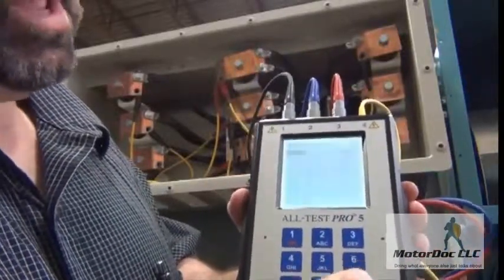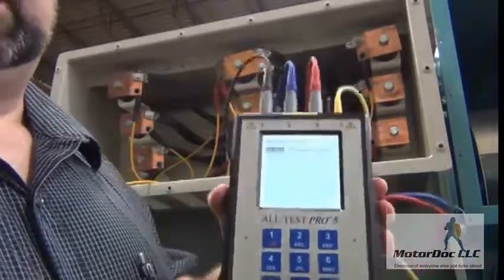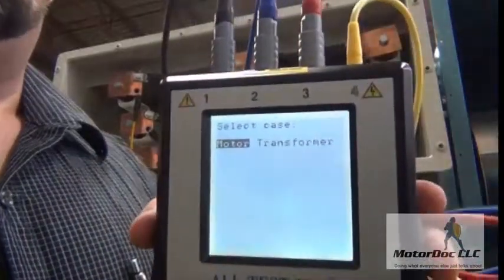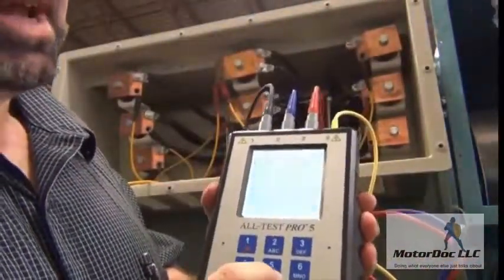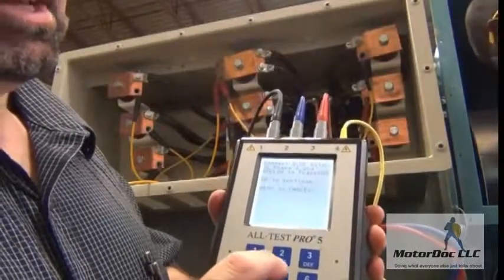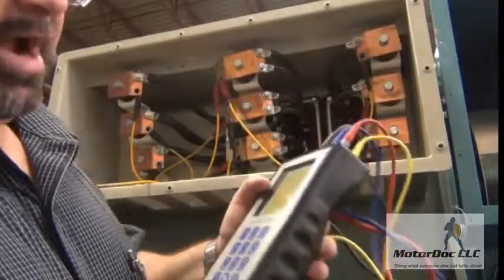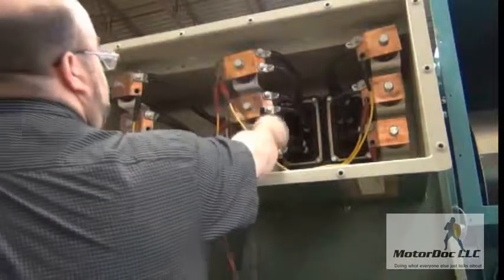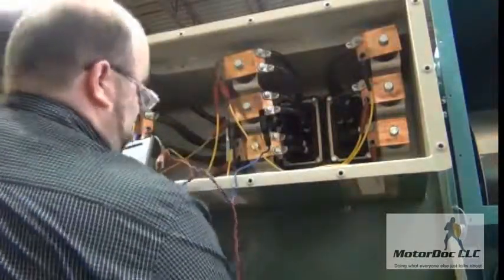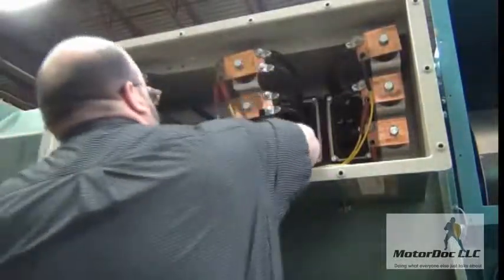If I click OK it says motor or transformer. This machine is designed to test motors and transformers as well as DC machines of all types. We're going to select motor. It says connect the blue clip to phase 2 and the yellow to any frame ground. So I take the blue clip to connect to phase 2 and connect to a ground inside the machine.